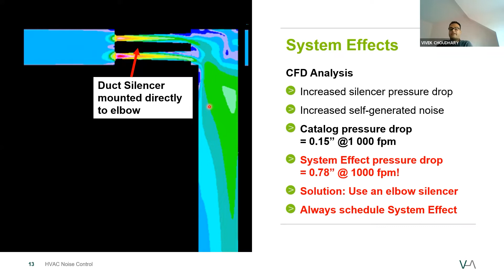But once we put that after this elbow and we calculate system effect pressure drop, which is based on the real inlet, which is an elbow, and real outlet condition, pressure drop is actually 0.78 inches at the same velocity. So again, this is not a right solution in this particular case. The right solution will be an elbow silencer, which will act as a duct silencer and an elbow silencer as well. So it will start from here and it will be an elbow all the way there. So basically it will have a better performance and a better pressure drop as well.